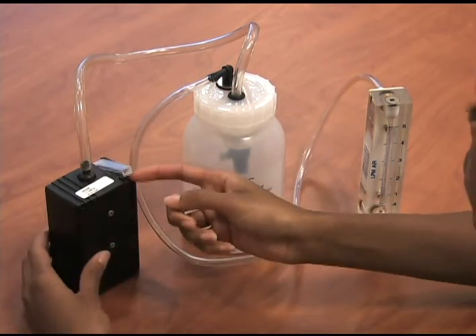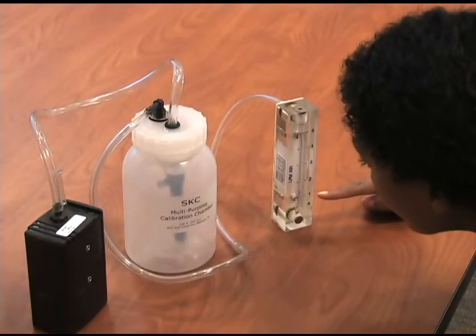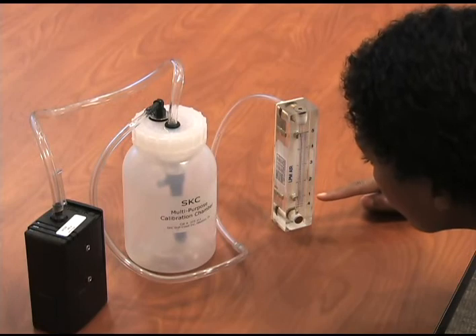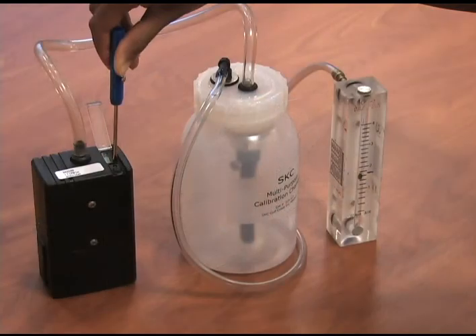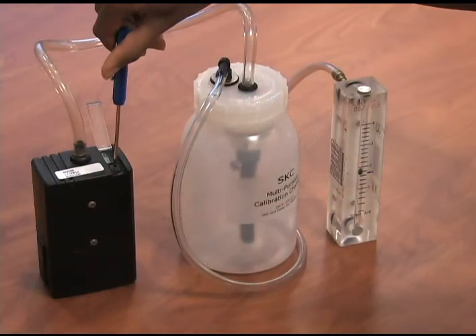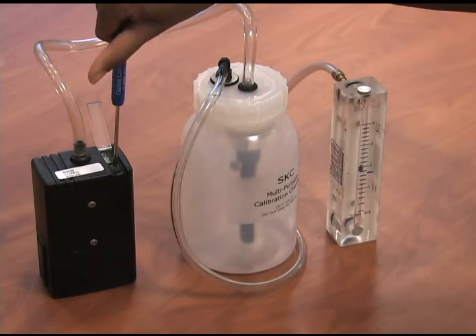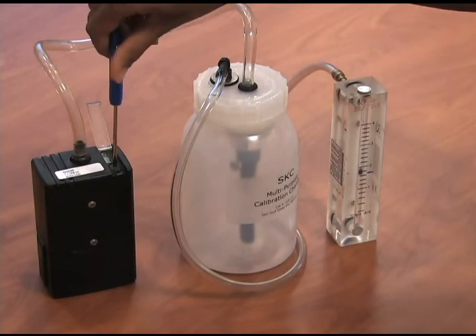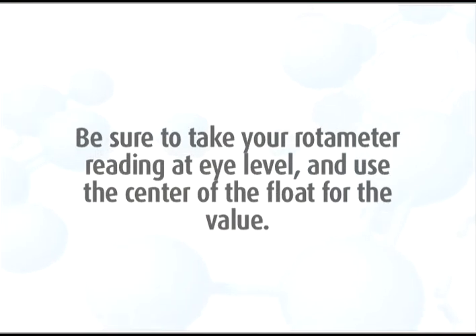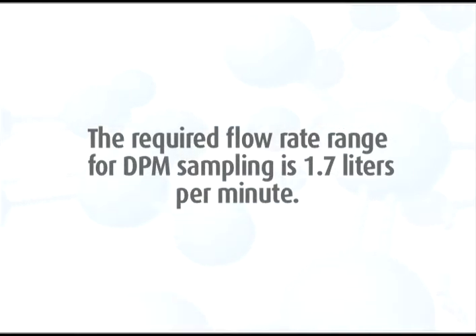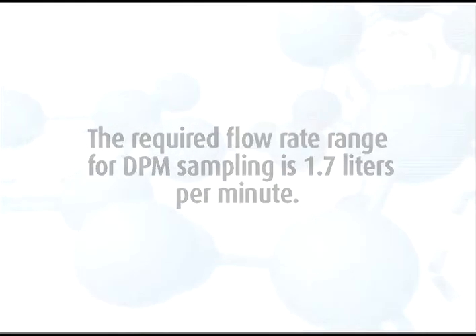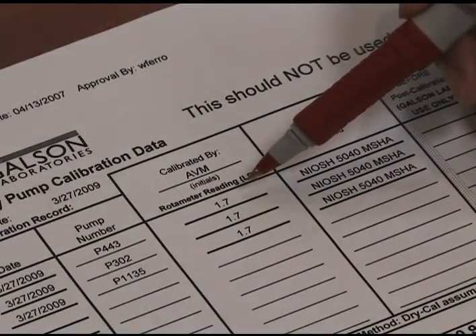Turn on the pump. With everything sitting on a level flat surface, check the ball float in the rotometer. Adjust the flow rate by turning the flow adjustment screw on the top of the pump until the rotometer indicates the desired flow. Be sure to take your rotometer reading at eye level and use the center of the float for the value. The required flow rate range for DPM sampling is 1.7 liters per minute. Verify the recorded flow rate on the pump calibration sheet.